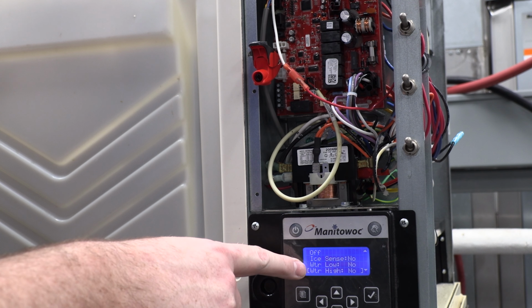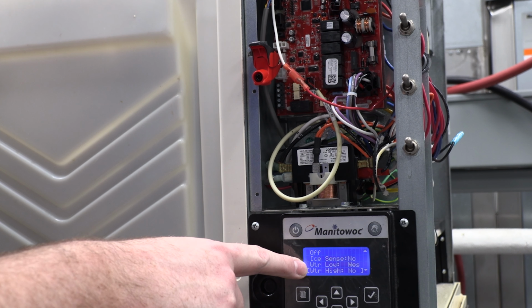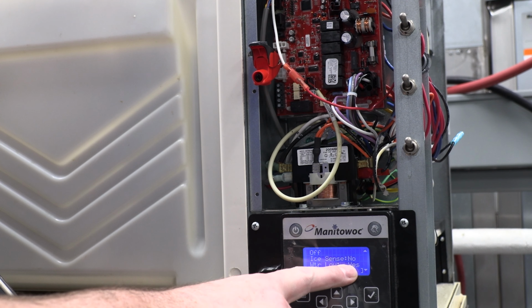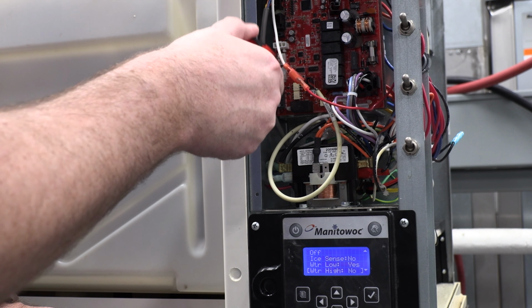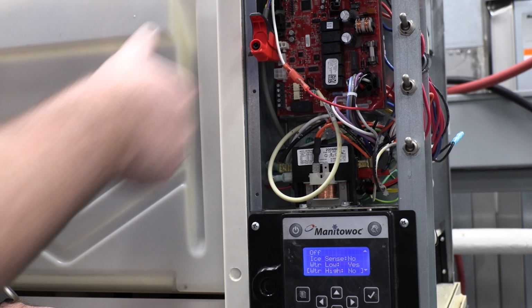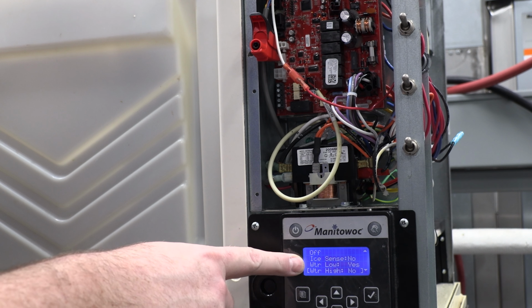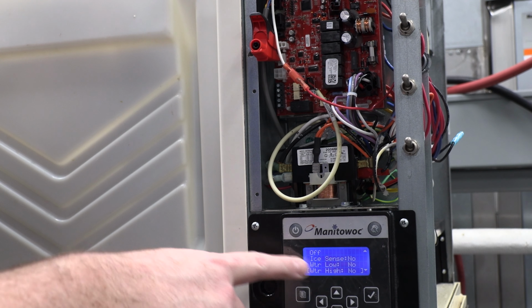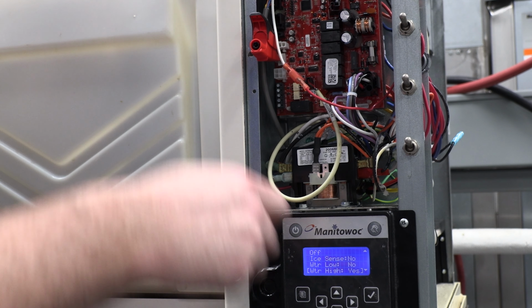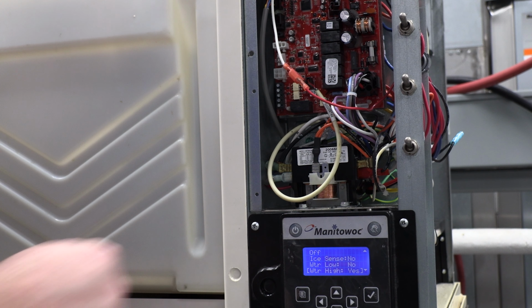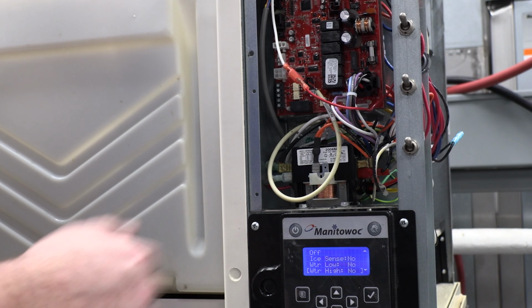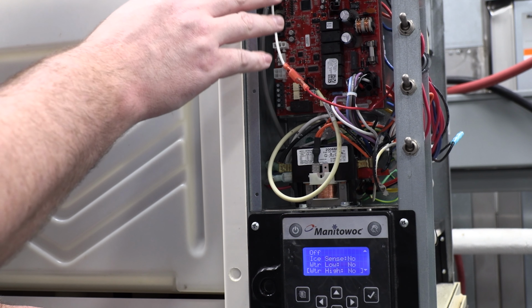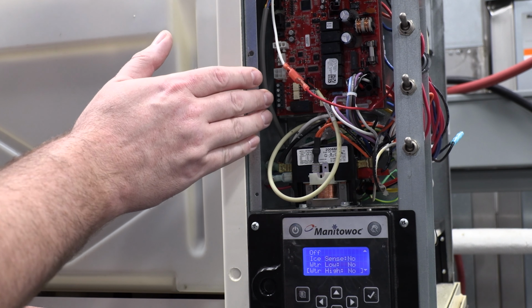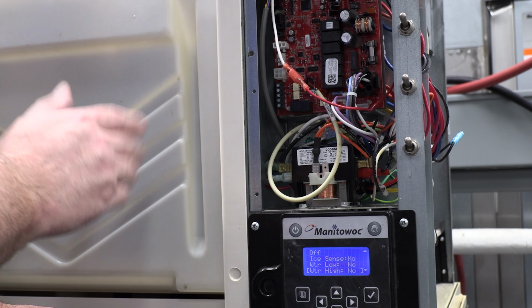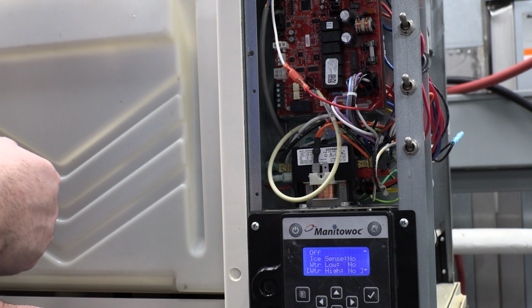And if we monitor our screen here, sometimes it takes a second to refresh. You'll see we are now reading yes, water low. If we then move our jumper over between H and C, you'll see after it refreshes, the low goes away and water high reads yes. When you have everything disconnected, you should be reading no, no. And there it goes. So at this point, we can confirm our control board is not the issue here. It's going to be something with the water level probe or the water level probe intermediate harness.